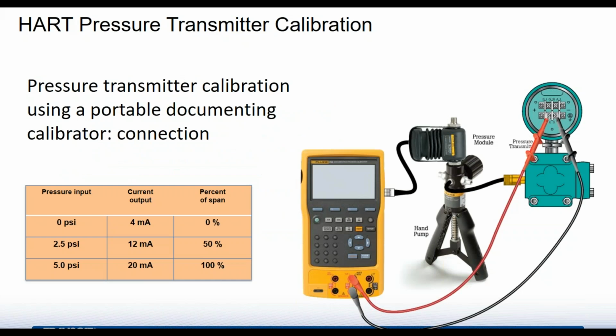So let's take a look at how a connection is going to look. Here's a simplistic version where you've got your calibrator on the left. In this case, we've got a Fluke 754, and you've got your red and black wiring going straight up to the transmitter to power it, to measure your 4 to 20, and to talk HART through this line. Then you're going to have a couple of different options.